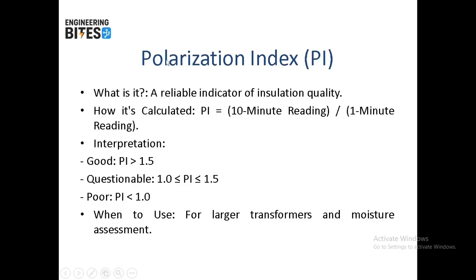And we can use the polarization index for larger transformers and the moisture assessment. It's a reliable indicator of insulation quality. It's calculated by dividing the 10-minute reading by the 1-minute reading. When the polarization index is higher than 1.5, it's considered good. When it's between 1 and 1.5, it's questionable, and when it's lower than 1, it's considered poor. And as we said before, it's used for larger transformers and moisture assessment.